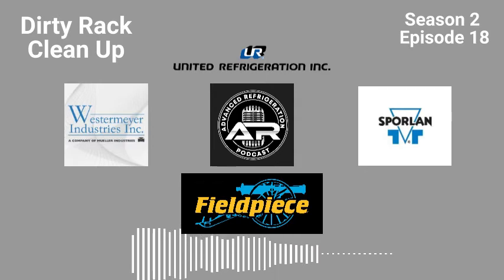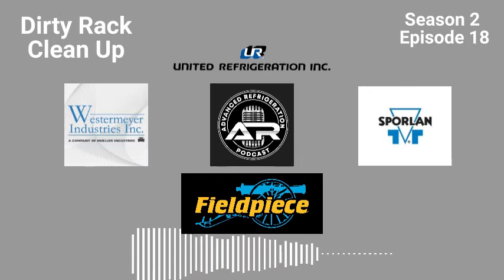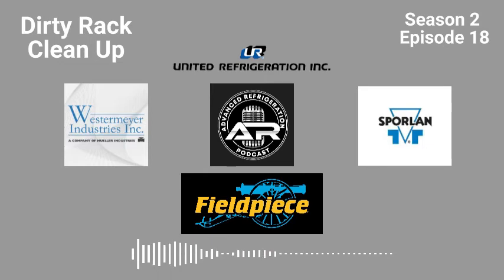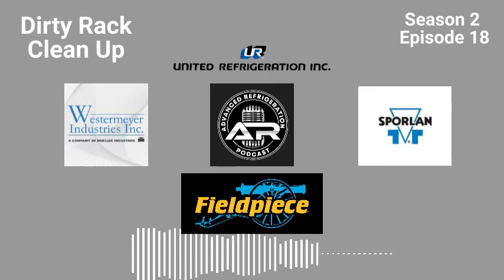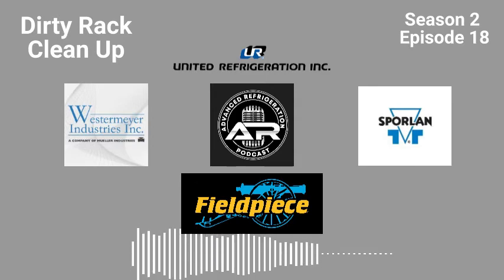So I pull these filters out, and I know when I'm cutting bolts off a suction shell, they haven't been done in forever. If you're cutting bolts off, there's a good chance, if you don't see the guts in the motor room, those things are probably still in there, and they're probably 10 years old. I did a gas change out, and on one rack we had 12 compressors and I had 9 crushed filters. Damn. There were 6 head compressors, 3 were changed, and 2 had died twice already, and nobody ever changed the suction filters. They were black as a tire, crushed, and oil logged.